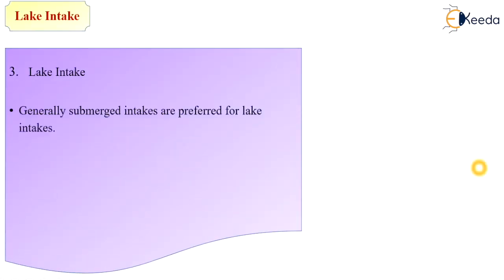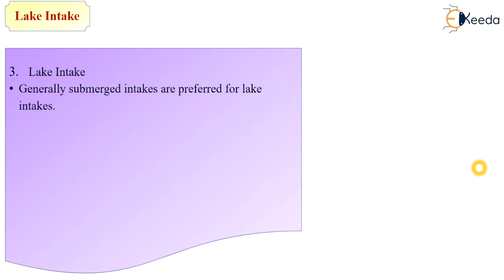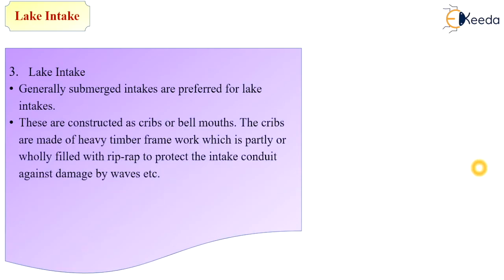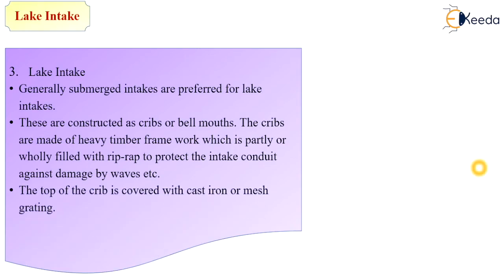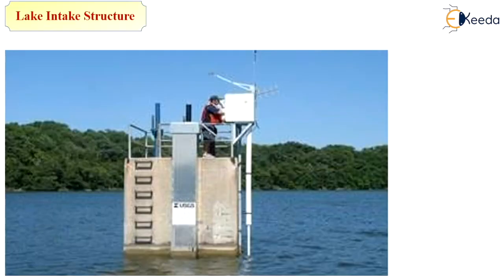Next is lake intake. Generally submerged intakes are preferred for lake intake. These are constructed at a crib or bell mouth. The cribs are made of heavy timber framework partially or wholly filled with rip-rap to protect the intake conduit against damage by waves. The top of the crib is covered with cast iron or mesh grating to avoid entry of silt particles or floating materials. This is the diagram of a lake intake constructed on or near the bank of the lake.